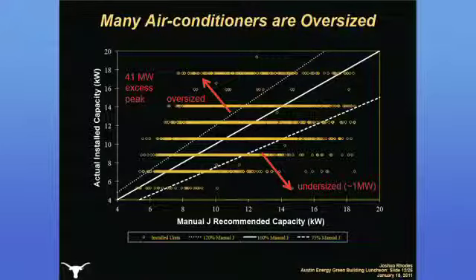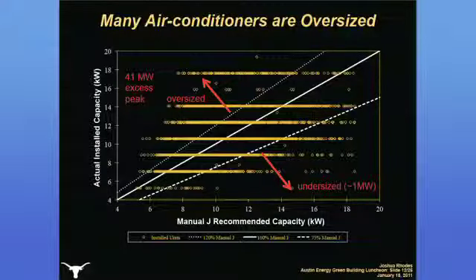So along the x-axis on the bottom is the Manual J recommended capacity. We took specifics off of the ECAD audits and we ran it through the calculation. Had to make some assumptions and came out with a recommended capacity. And then the actual installed capacity, just measured off the nameplate of the unit, is on the y-axis. Now the solid line is 100%. So if the unit that's installed actually corresponds to what we measured it should be, it would be clustered around that solid line. The dashed line down below is 75%.